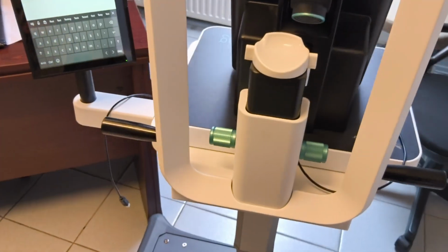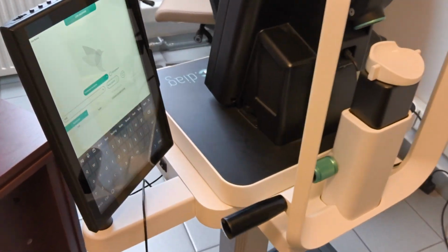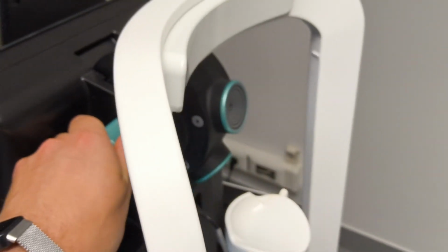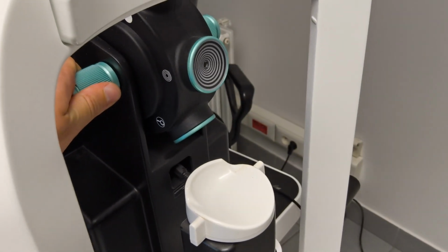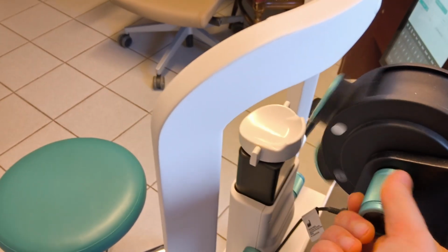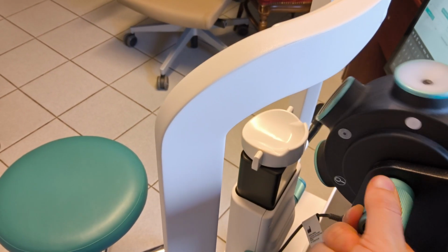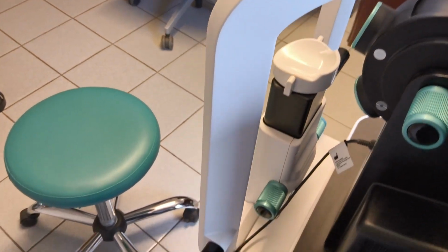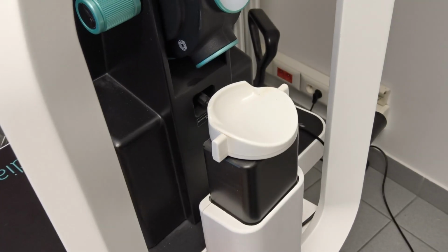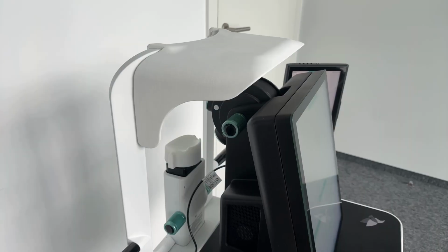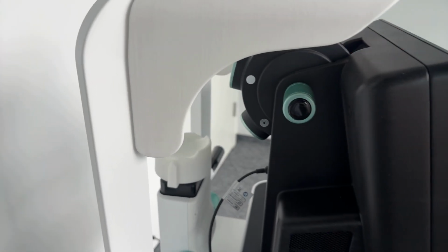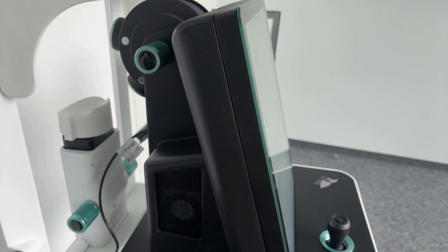This tablet is mostly used for showing the patient the results, and then you have the manual knobs, and those manual knobs are used for changing the light source. So you can use the Placido, you can do magnification, or you can use the cone for lipid related parameters. There is a knob for moving the chin rest up and down. Newer models, they have this kind of roof over the C.DIAG, but ours is fine. It doesn't really affect the measurement.